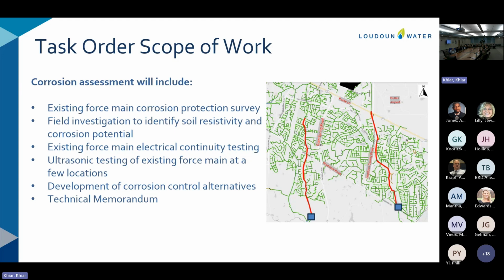After this preliminary field work is completed, we will also expose the pipe — this is difficult and expensive, so we have to be selective — identifying 6 to 8 locations where we'll expose the force main, visually inspect it, and perform ultrasonic testing to understand if deterioration has already started or what the condition of the pipe is. How many locations we do will depend on the preliminary findings.